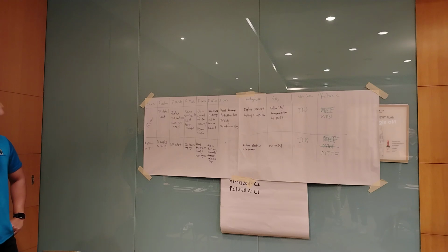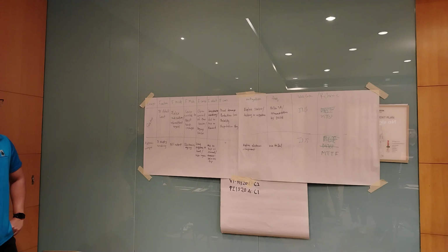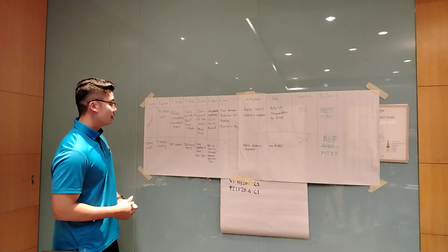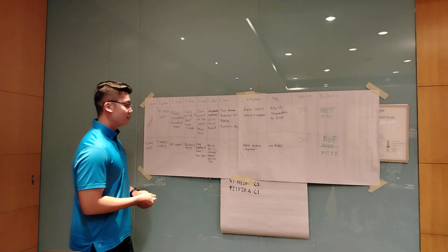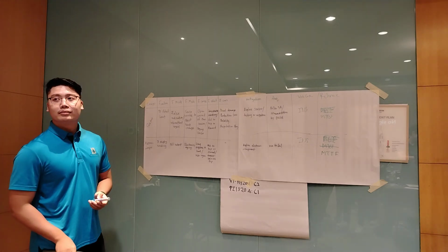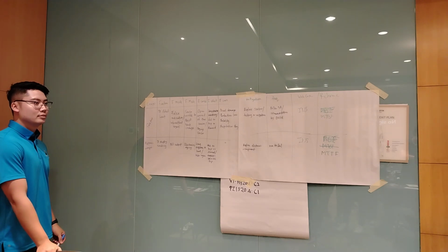Correct. There should be some more here. The electronic component, not only replaced after 2 years. Fail, then you replace. What else do you need to do? I think for electronic components we can't do much, because it's small and it's not worth changing a small part. Changing the whole thing is cheaper compared to changing the small electronic parts. And one more thing, this one is quite tricky because it's a hidden failure. You only come to know it when it has already failed. So in instrumentation there are a lot of hidden failures. That's what we did.